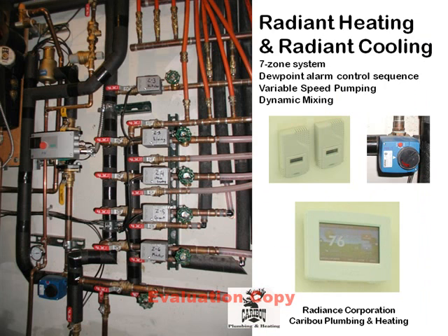Individual thermostats in each of the 7 zones control the flow of heating or cooling water to the radiant floors by turning on or off its associated zone valve. Hydronic flow rate is controlled using variable speed circulation pumps. Cooling water set point temperature is dynamically changed based on slab temperatures by modulating the position of a 3-way mixing valve.